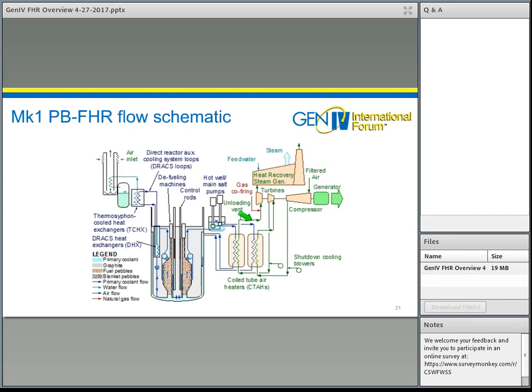And so at 670 degrees, this air then expands down to atmospheric pressure, and then residual heat is removed in this heat recovery steam generator. Gas co-firing in this location can boost the temperature going into this turbine and therefore boost the power output. And the dynamic response of the power conversion system for the nuclear air combined cycle can be about 3 times faster than in a conventional combined cycle plant, because you're already hot and spinning with a constant airflow rate going through the power conversion system.